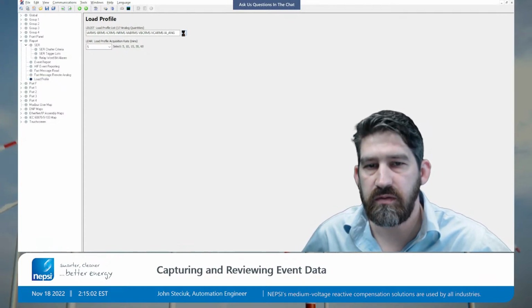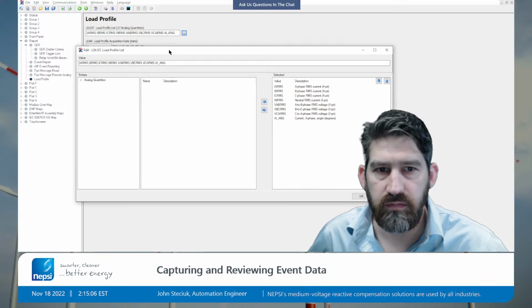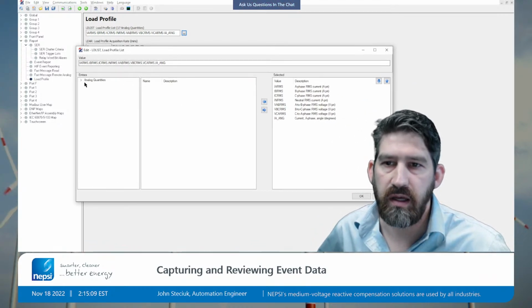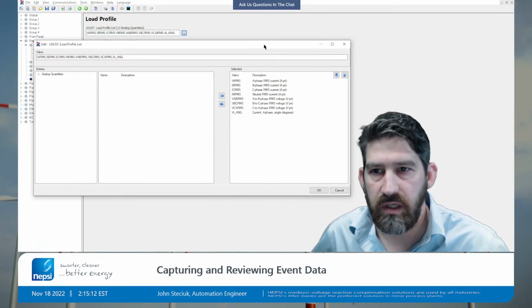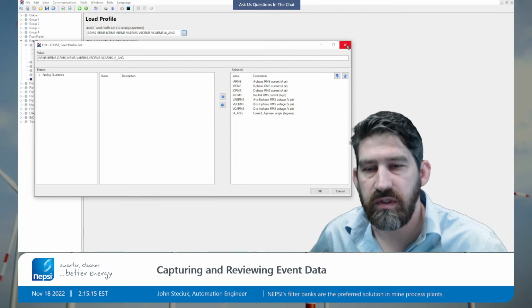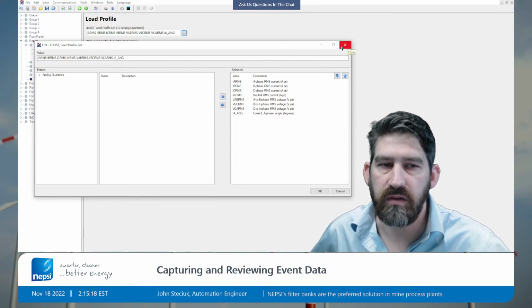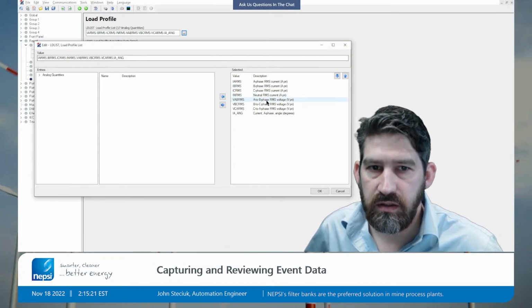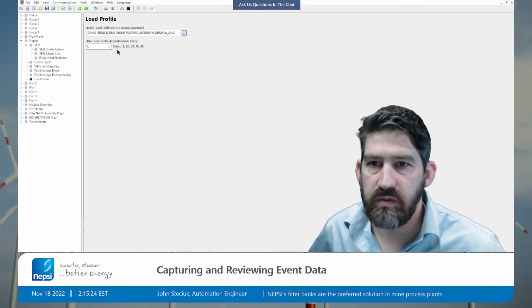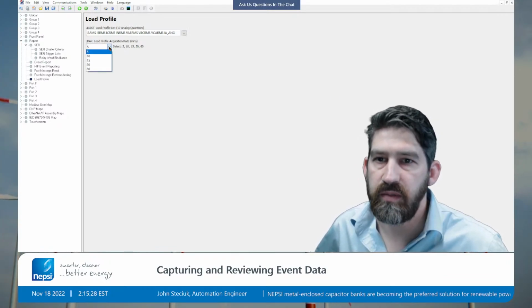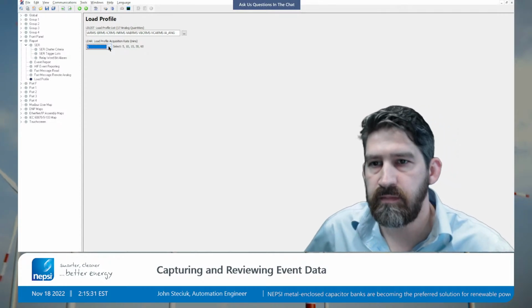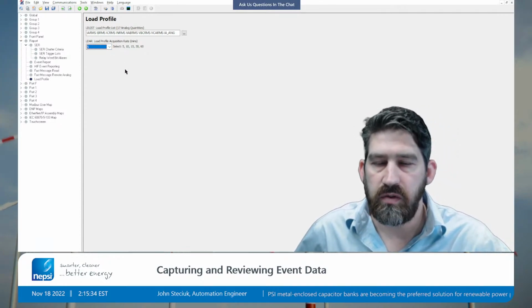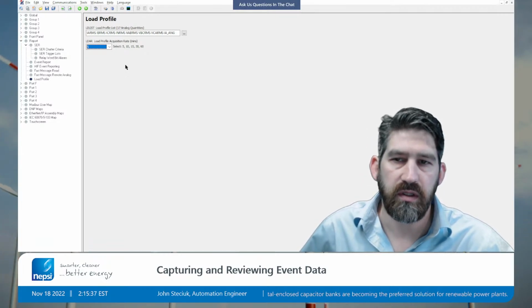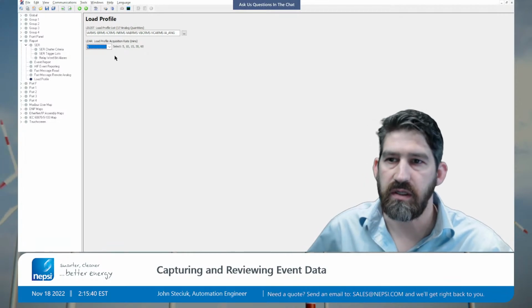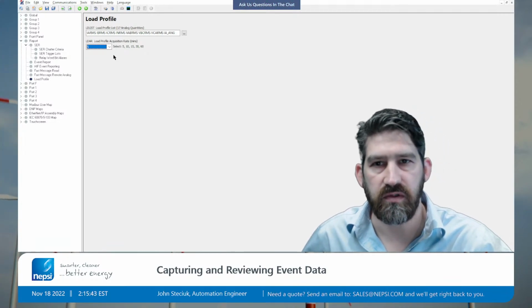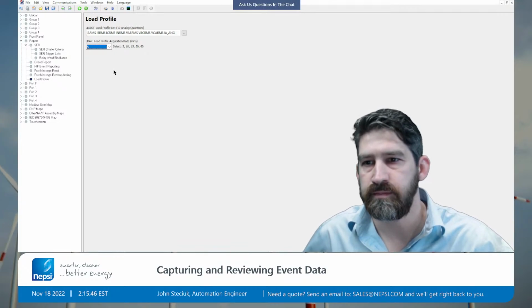There's a load profile list where you can again specify different values to log analog quantities at different intervals. This is more for like long-term logging. The intervals for acquisition rate are 5 minutes, 10 minutes, 15, 30, and 60 minutes. So you can look at the load profile report, and you can export that data into Excel, and you can chart different analog values, and it's very useful for long-term trending.